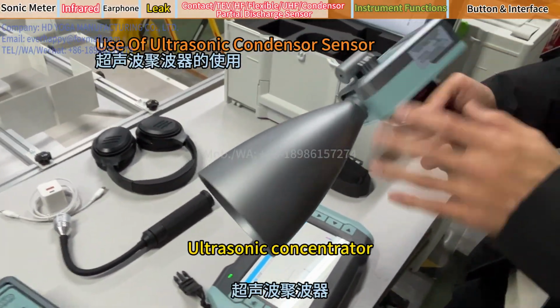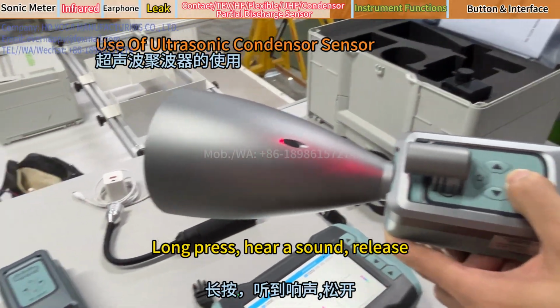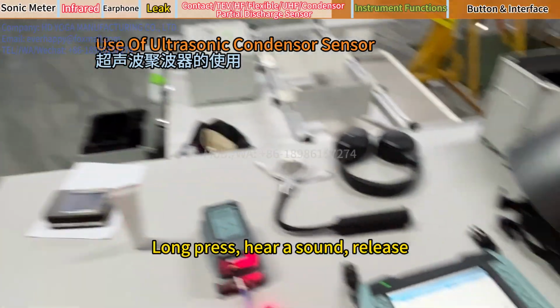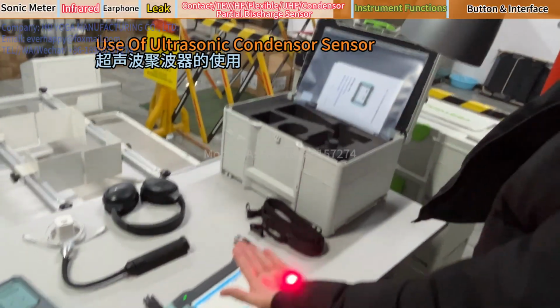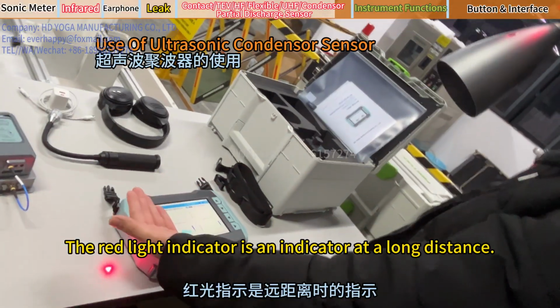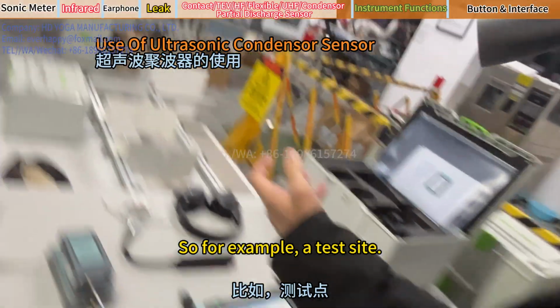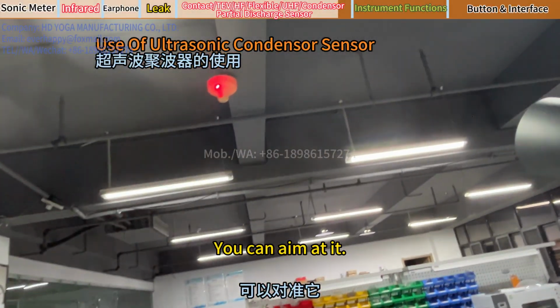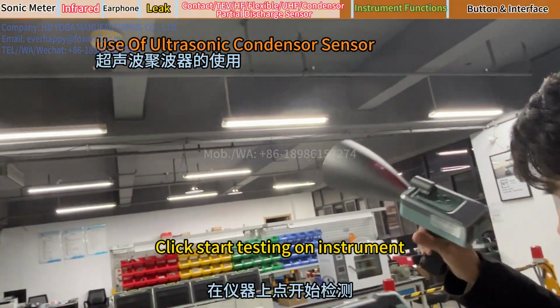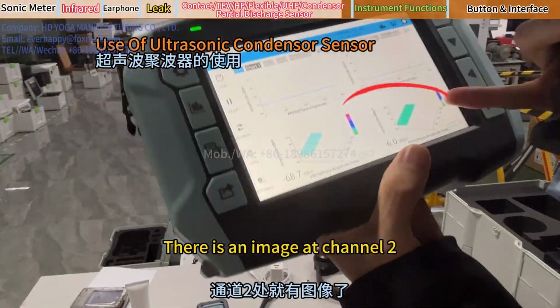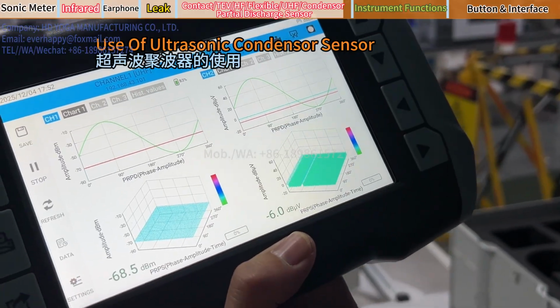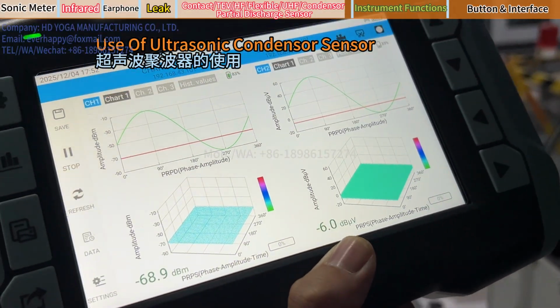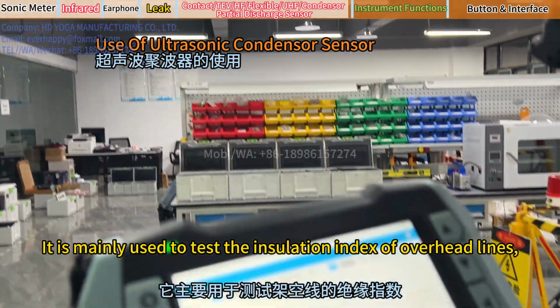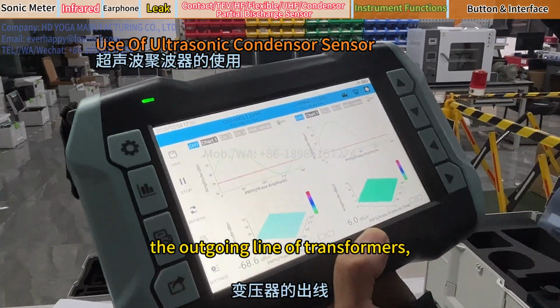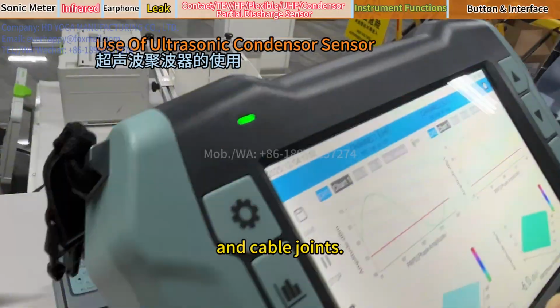Ultrasonic concentrator. Open. Long press, hear a sound, release. There is a red light indicating. The red light indicator is an indicator at a long distance. So, for example, a test site, you can aim at it. Click Start Testing on the instrument. There is an image at channel 2. If the value fluctuates, it indicates that there is interference. It is mainly used to test the insulation index of overhead lines, the outgoing line of transformers, and cable joints.